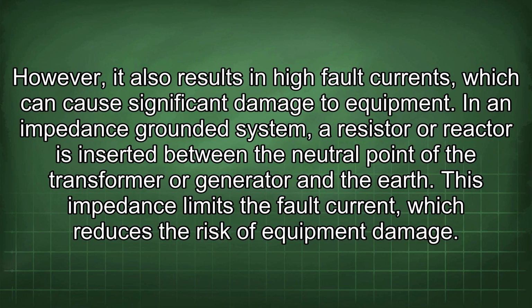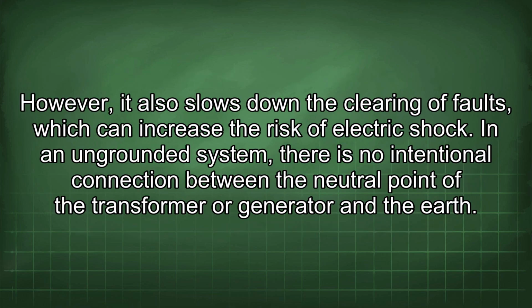In an impedance-grounded system, a resistor or reactor is inserted between the neutral point of the transformer or generator and the earth. This impedance limits the fault current, which reduces the risk of equipment damage. However, it also slows down the clearing of faults, which can increase the risk of electric shock.